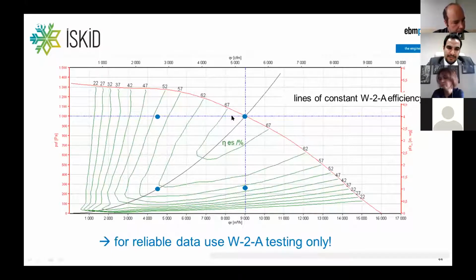If it's a constant pressure part load, so half the flow, coming from 68%, it's down to 52. Even along the resistance curve, where the fan efficiency doesn't change much, you see we come from 68 down to 61, more or less. This is related to the motor and to the drive. Or if you come down along the constant volume, it's down from 68 to 54 or something like that. And reliable data in part load can't be calculated because the basis is not there, the data of the different components.